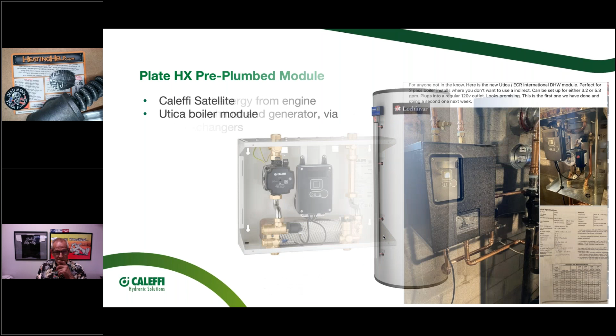So that was one of the questions that came in about oversizing. Again, this will show you that as you start putting data in here and you start putting in a fouling factor on that, and if you know how to enter that information based on hardness of the water, you can see as this number changes how the performance and the efficiency of this heat exchanger is changed by that. So, we want not only a lot of surface area, but we want clean surface area to get the best heat transfer. Let me see if I had anything else on that.